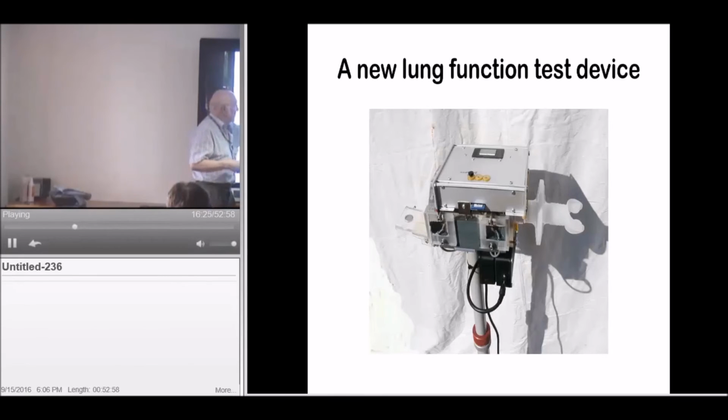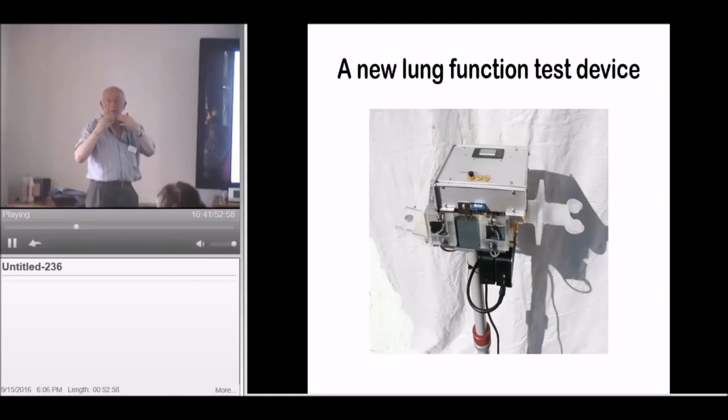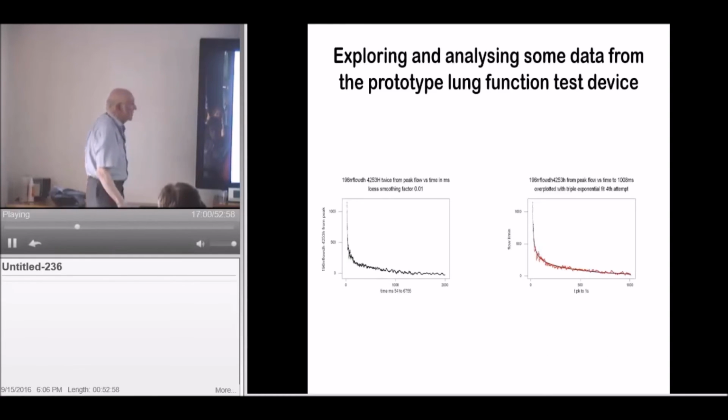It's a very novel way of looking at lung function. It has a flap valve here, and you blow in there, and at a certain pressure the flap valve opens suddenly. It's like doing a cough. And what you get out of it, you have crossed ultrasound beams measuring the velocity of flow once you open the flap valve. And it seemed able, on some limited trials, to distinguish between types of lung disease that were very difficult to detect by normal means.